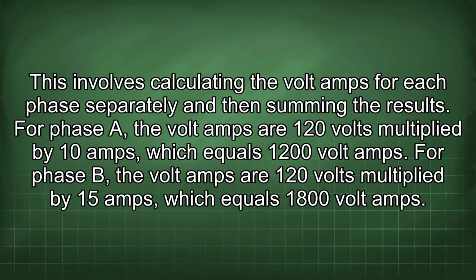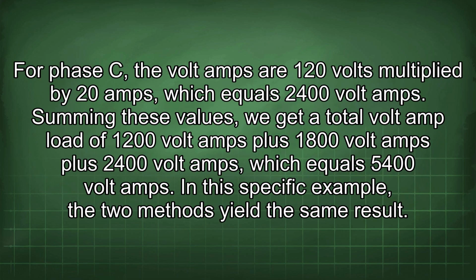This involves calculating the volt-amps for each phase separately and then summing the results. For phase A, the volt-amps are 120 volts multiplied by 10 amps, which equals 1200 volt-amps. For phase B, the volt-amps are 120 volts multiplied by 15 amps, which equals 1800 volt-amps. For phase C, the volt-amps are 120 volts multiplied by 20 amps, which equals 2400 volt-amps. Summing these values, we get a total volt-amp load of 1200 plus 1800 plus 2400, which equals 5400 volt-amps. In this specific example, the two methods yield the same result.